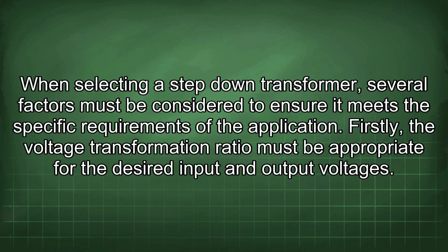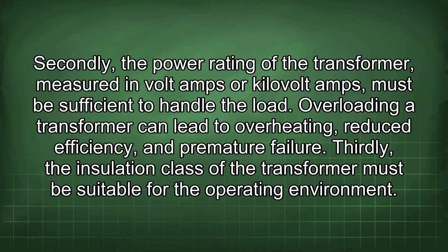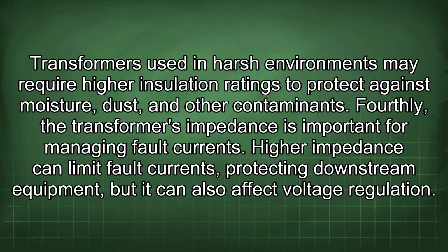When selecting a step-down transformer, several factors must be considered to ensure it meets the specific requirements of the application. Firstly, the voltage transformation ratio must be appropriate for the desired input and output voltages. Secondly, the power rating of the transformer, measured in volt-amps or kilovolt-amps, must be sufficient to handle the load. Overloading a transformer can lead to overheating, reduced efficiency, and premature failure. Thirdly, the insulation class of the transformer must be suitable for the operating environment. Transformers used in harsh environments may require higher insulation ratings to protect against moisture, dust, and other contaminants.